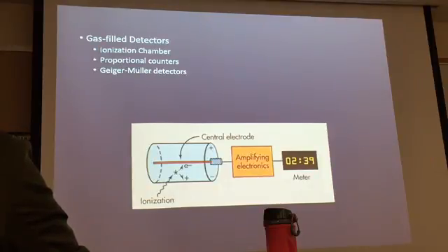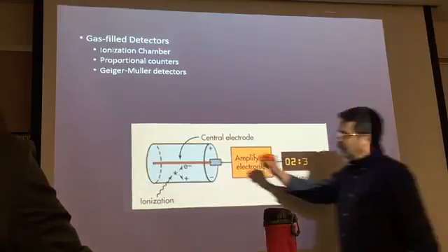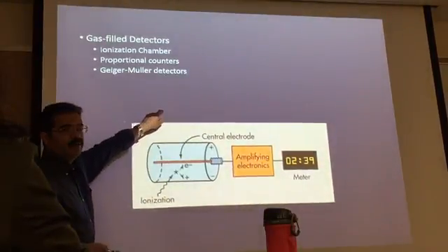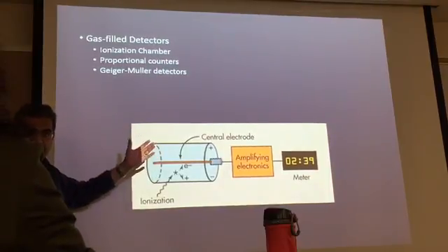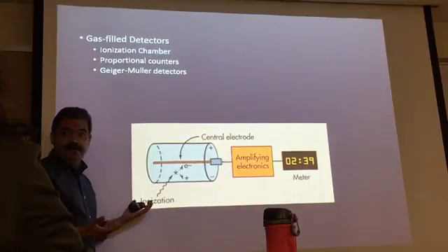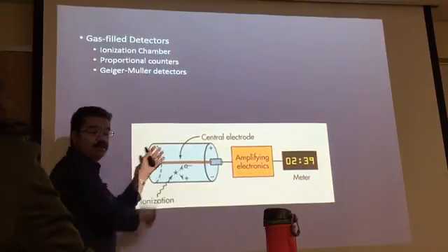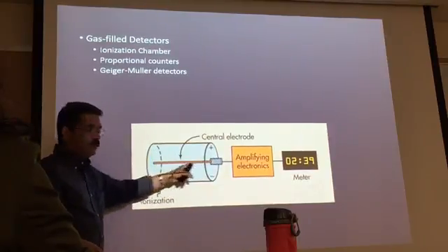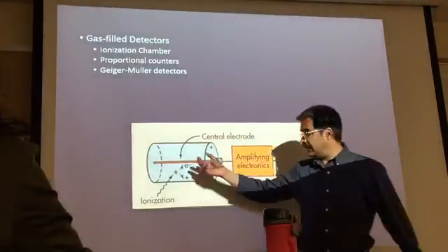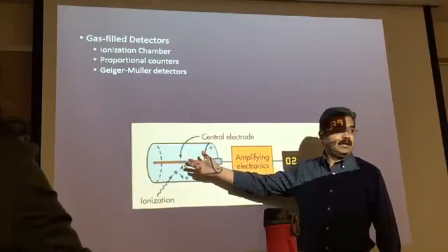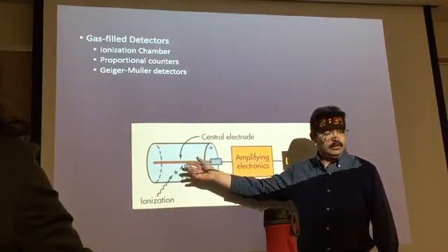Okay? What is important to remember is that as the voltage increases, they become more sensitive. They can catch radiation very quickly. And why is that? Say you have one X-ray photon coming in, it breaks a molecule, okay? The molecule is broken apart, then you get ions out of it, right? And there is an attractive force from the wall and from the central electrode to attract those ions. So very quickly the ions are attracted. There is no recombination, or if there is, it's minimal.